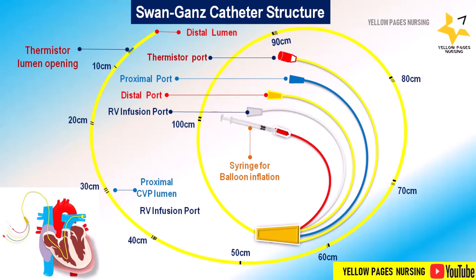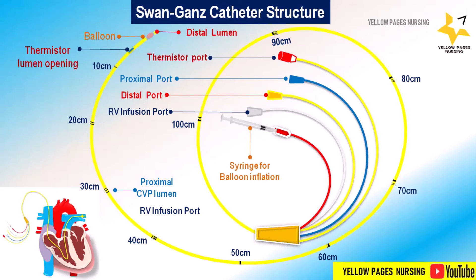Next is the balloon inflation valve with a syringe attached to it. The maximum volume is 1.5 cc of air inside the balloon. The balloon is located near the tip of the catheter and is inflated while the catheter is positioned in a branch of the pulmonary artery.